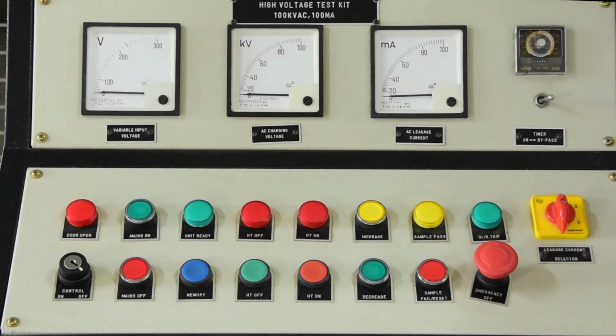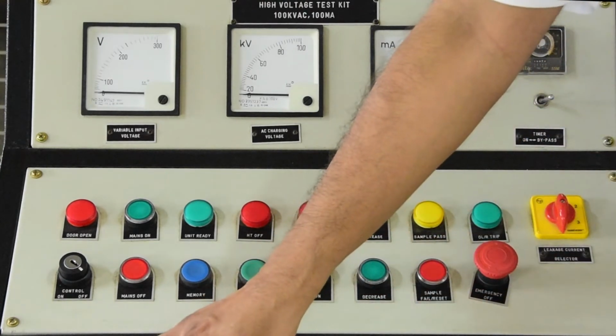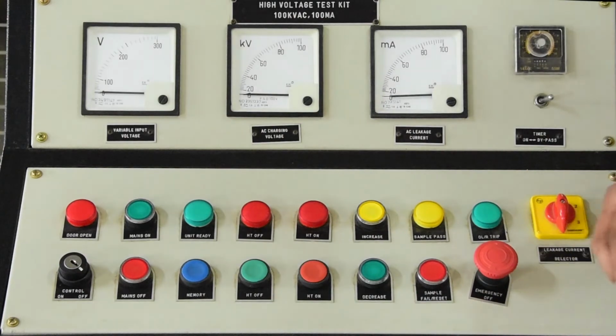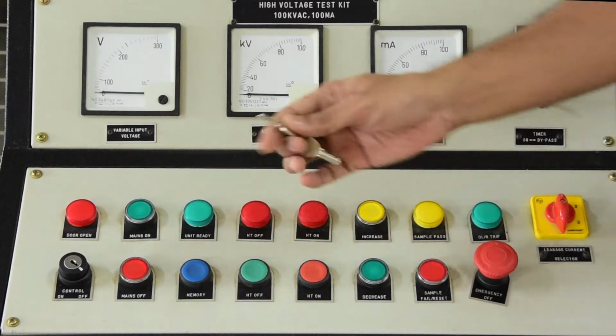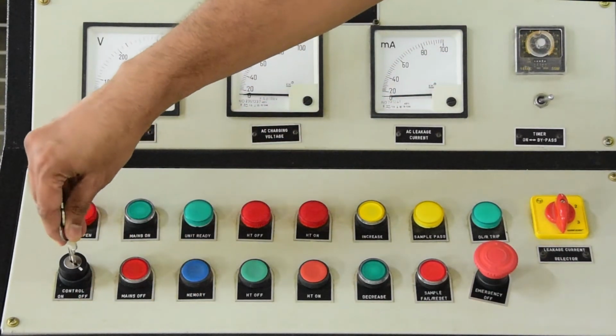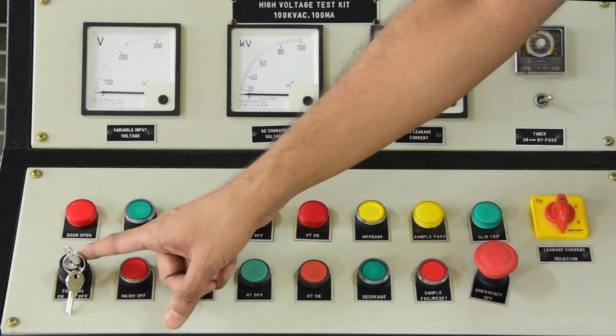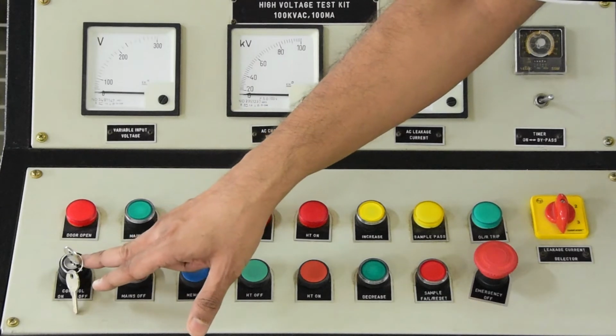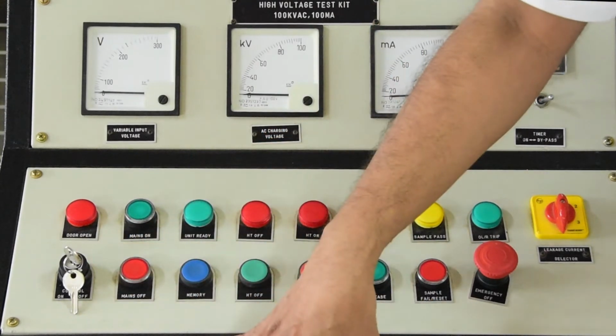We have already seen the arrangement of cascade transformers, the sphere gap assembly, and all the assembly inside the cage. We have also seen how we stand outside the cage, closer to this particular control panel, which has various sections. You can see first and foremost a switch here, that is an MCB. Apart from the switch, there is a key control on the left hand side. These keys are actually a safety feature. For safety purposes, a key type of input is required. Unless the keys are there, no one will be able to switch on the high voltage supply.